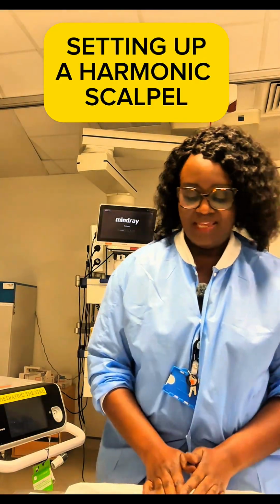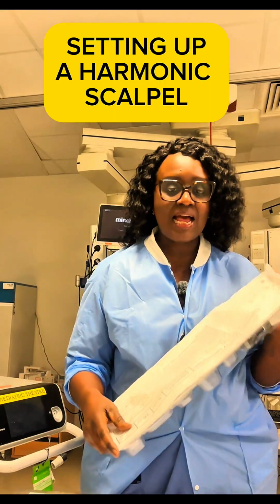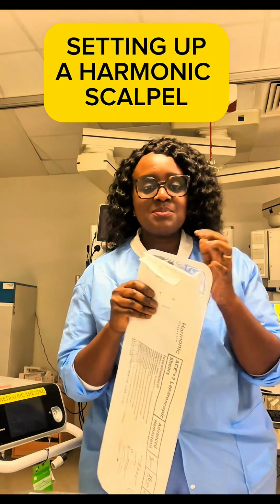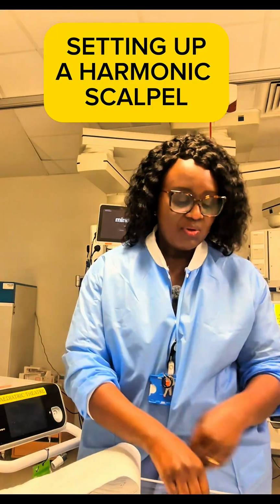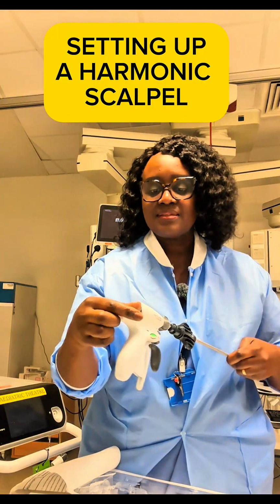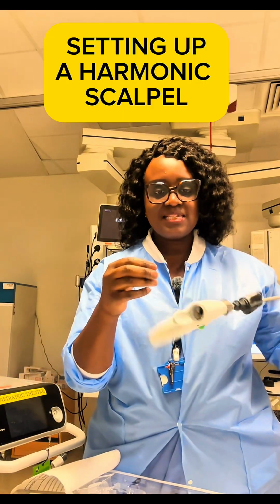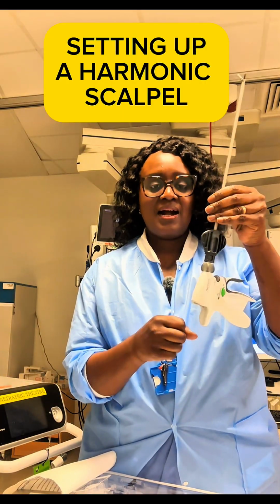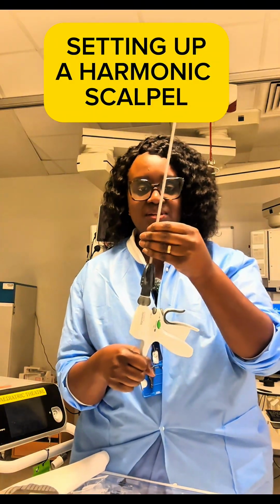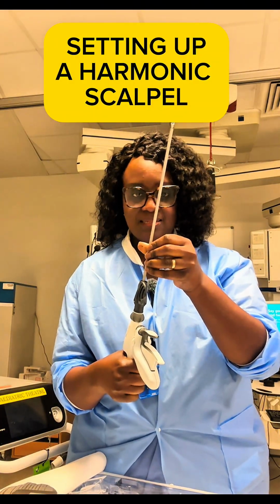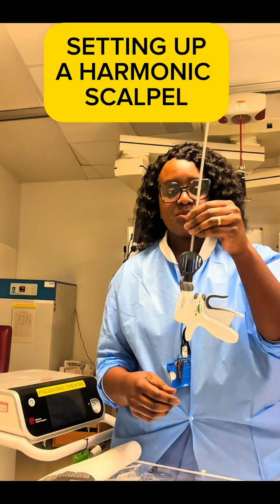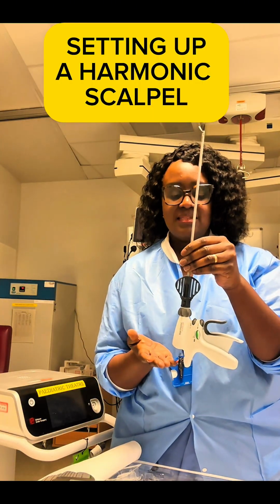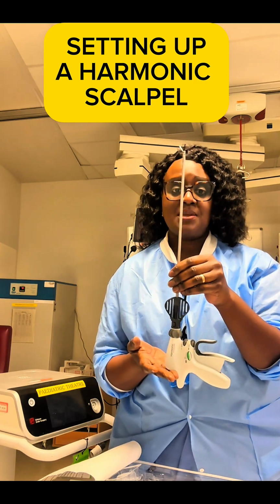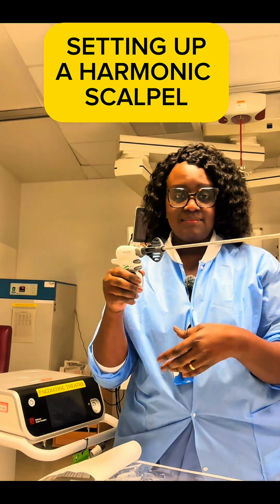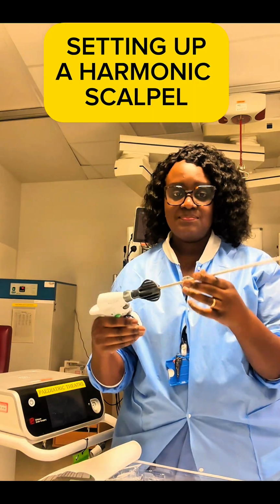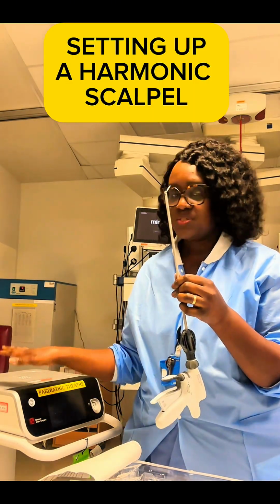Today we are going to talk about setting up a harmonic scalpel. There is the one that comes connected. The handpiece comes with a cable that connects to the machine, and there's this piece that you have to use, a handpiece that is re-sterilized before use. It's not disposable. So today I'm going to demonstrate how to connect the handpiece, the non-disposable handpiece, to the harmonic electrosurgical piece, which is by Ethicon, to the machine.